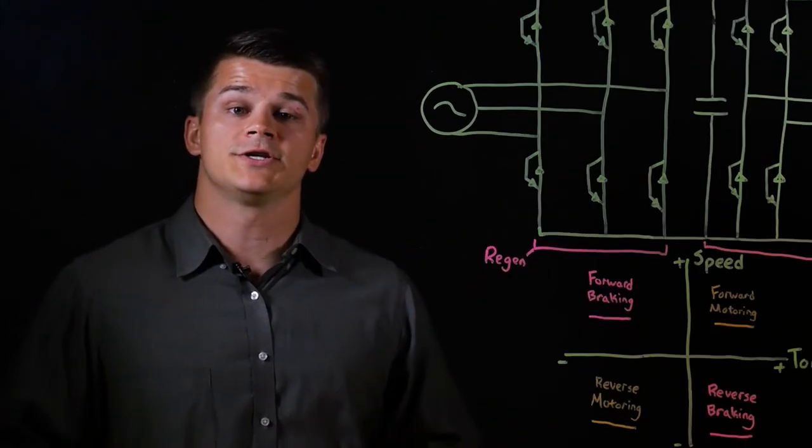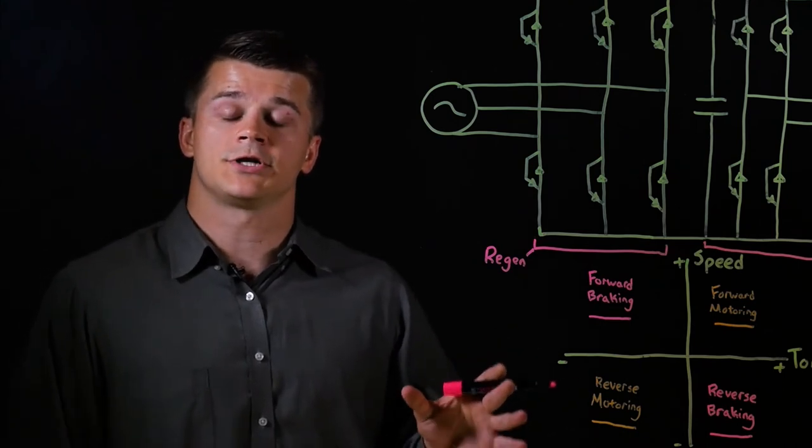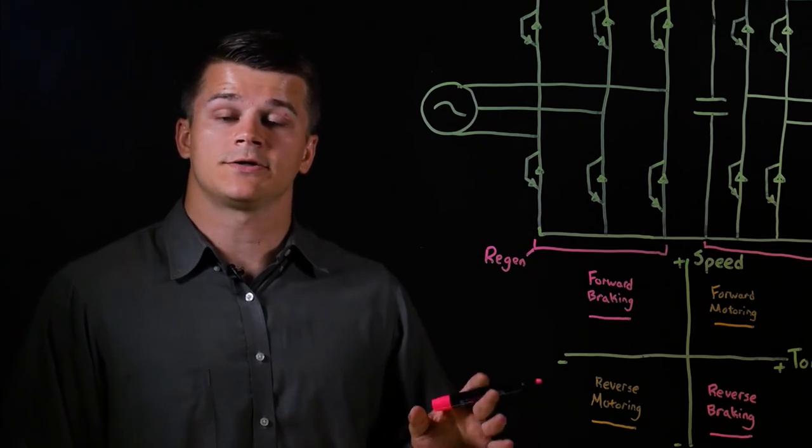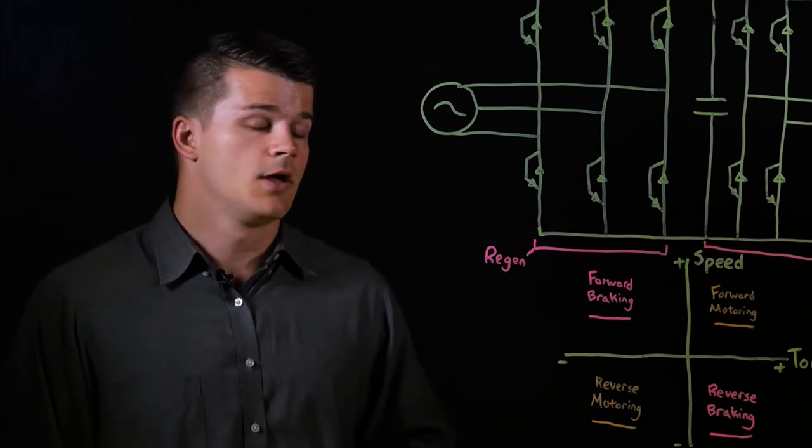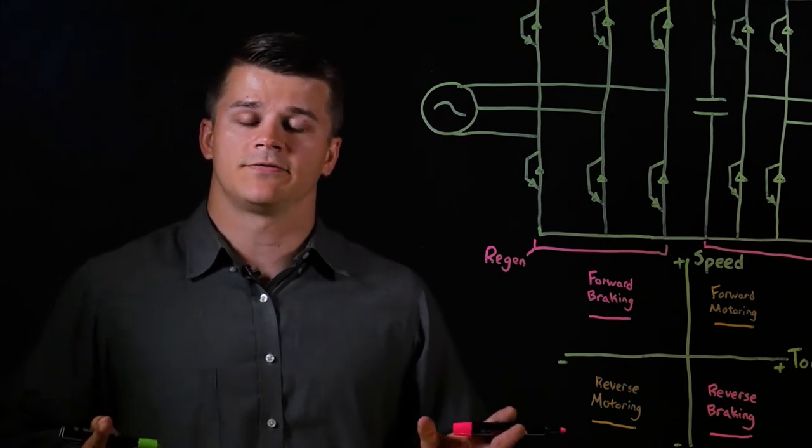The benefits of a line regen unit are that it reduces your net energy consumption and thus your energy costs. It also eliminates the need for a braking resistor, which increases the heat in your electrical cabinet and requires cooling. Finally, because it reduces your net energy consumption, it's environmentally friendly.